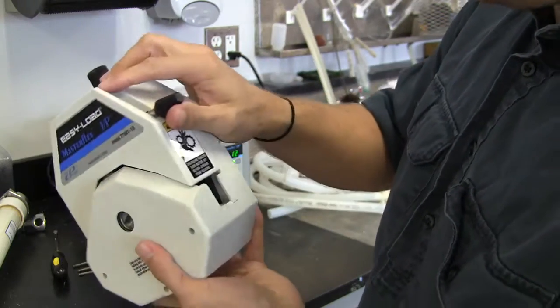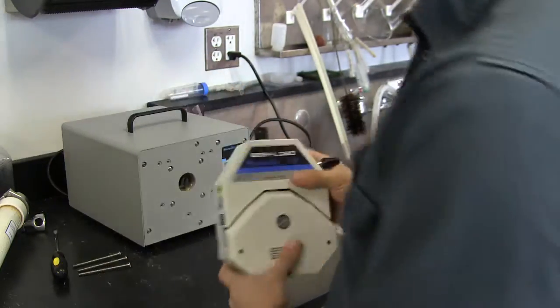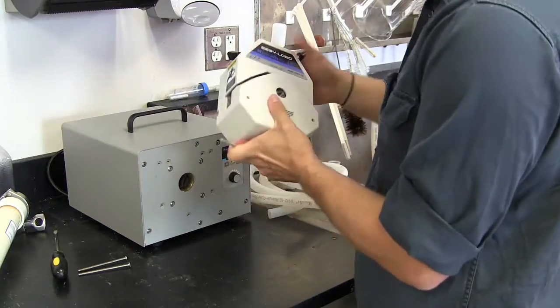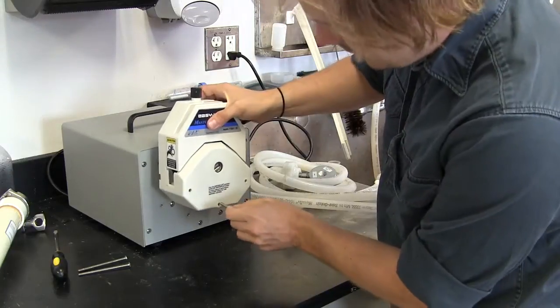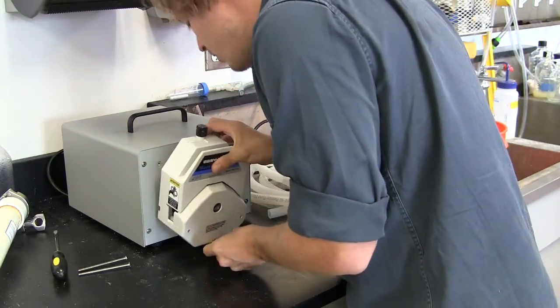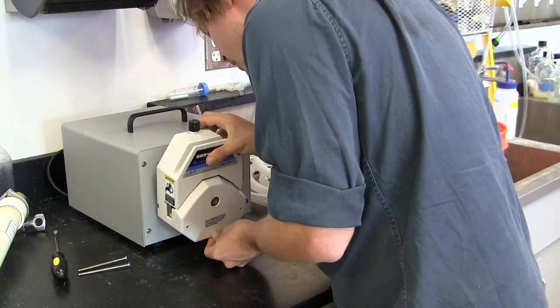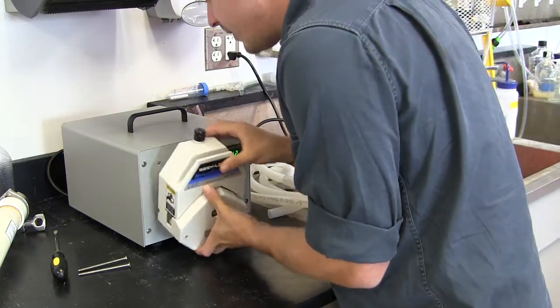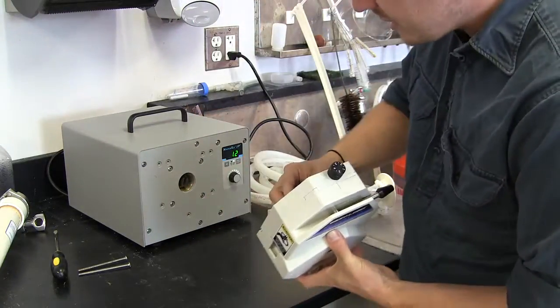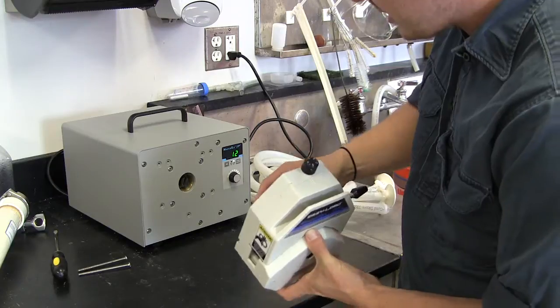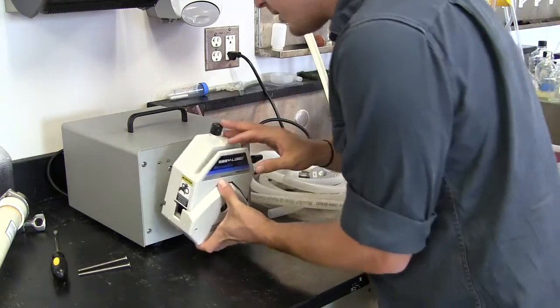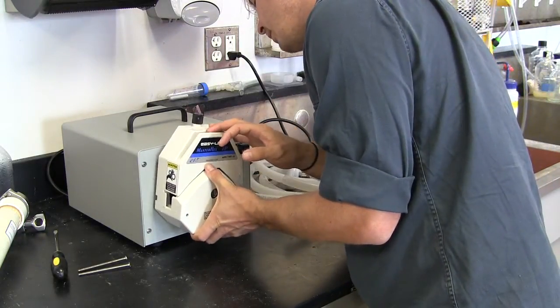If you're doing finer tubing, then you tighten it down. Okay. So what we'll do is we'll stick the head on, and we'll leave it clamped down so it's easier to handle. All you do is you put the bolt through and line it up with the first hole. What you also may have to do is line up the piece that sticks out of the pump head with the slot on the peristaltic itself so it will actually slide in.